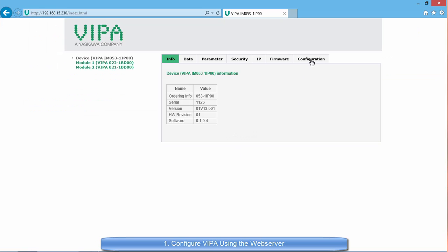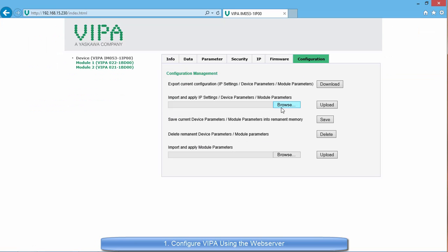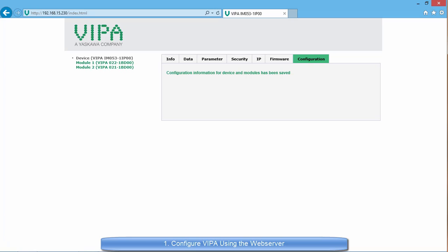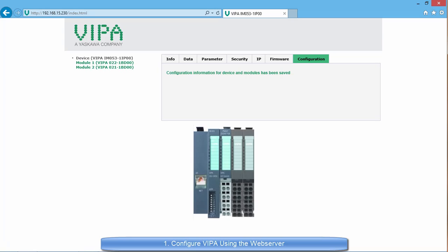When the web server appears, I can go into the Configuration tab and click on Save. This configures the interface module to know that two slice IO cards are attached to the device. This needs to be performed every time you add or remove a slice from the SLIO system.